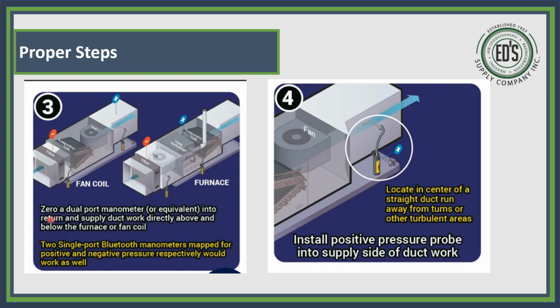All right, then you stick the P1 into the return and supply duct directly above or below the furnace or fan coil. Two single port Bluetooth manometers mapped for positive and negative pressures respectively would work as well.